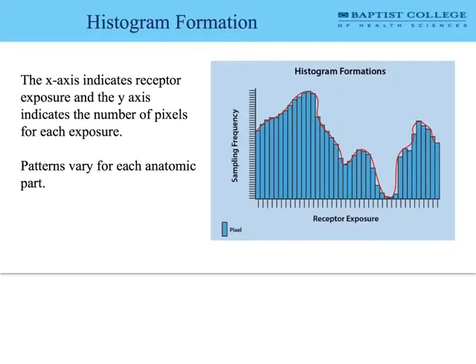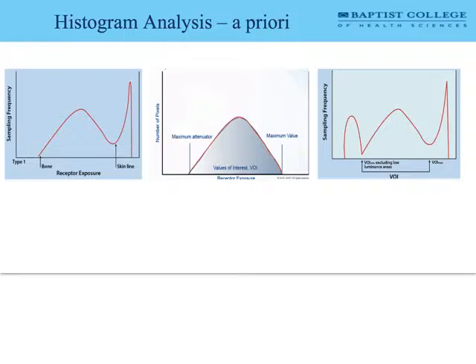During data acquisition, the histogram is the value distribution of the quantized data. I've represented it graphically here for clarity, but understand the computer is not looking at a graphic — it's looking at a table, and that's how it actually processes this data. There are two basic formats the computer uses to analyze histograms and produce images. The first is a priori histogram analysis, which has three basic types.